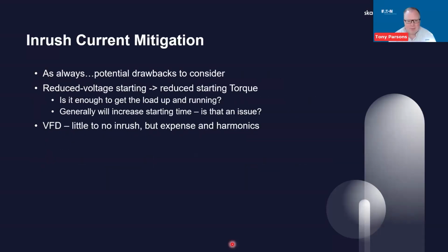As always, there are potential drawbacks to consider with those reduced voltage starting methods. Reduced starting torque results from the reduced voltage, so is that torque enough to actually get the load up and running? If it is, the reduced torque generally means you're going to have longer starting times. Is that going to create an issue?